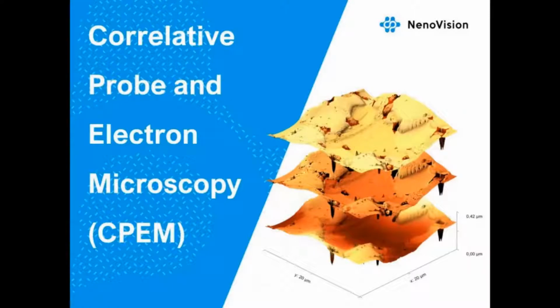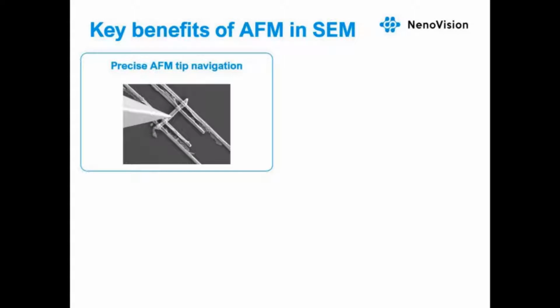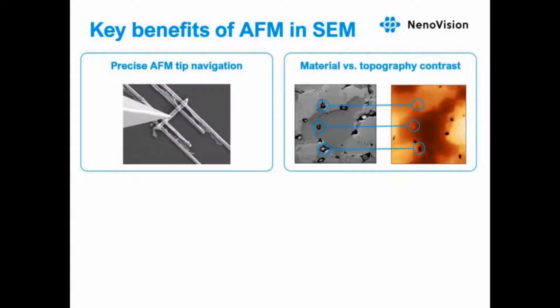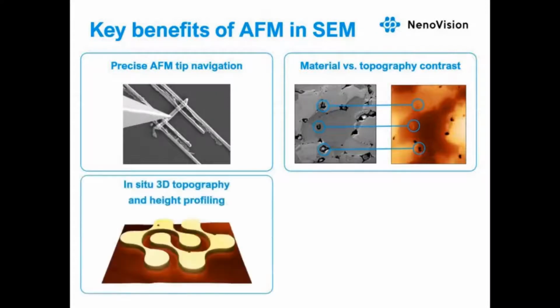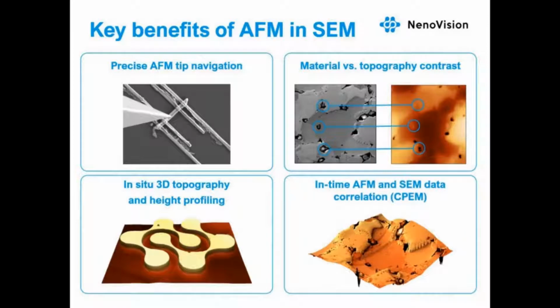And that leads us to the key benefits of the AFM in SEM approach. So first of all, it is extremely useful to utilize SEM for precise AFM navigation. Then it provides clear difference between material and topography contrast. Next point is 3D profiling of nanostructures in in-situ conditions, which is crucial for surface modification using, for instance, focused ion beam or gas injection system, and also for sensitive samples. And lastly, it allows for in-time AFM and SEM data correlation by a technique we call CPEM.